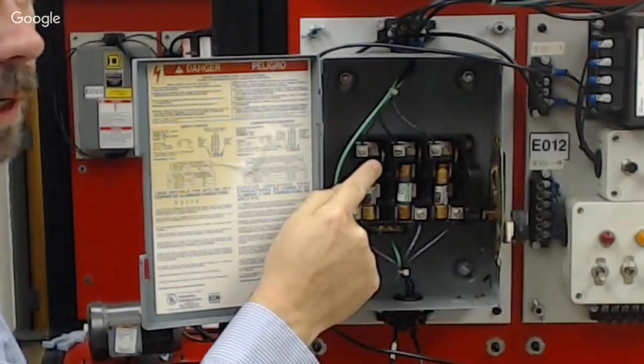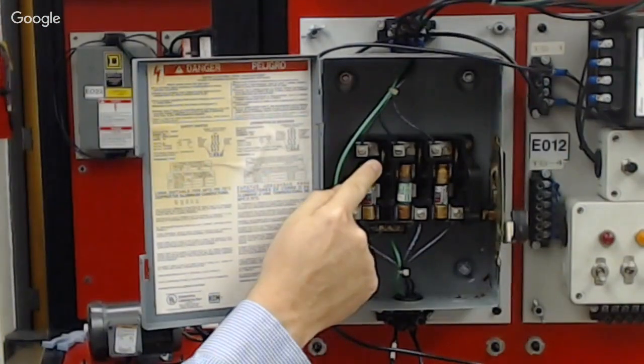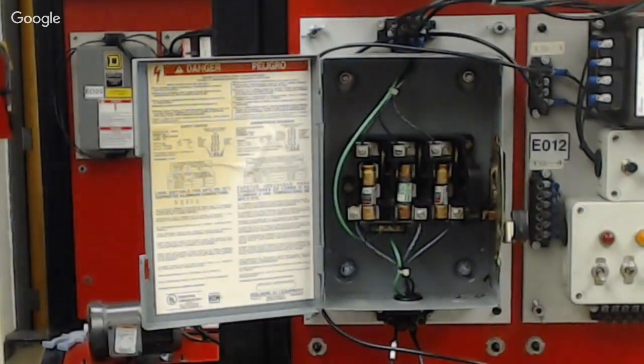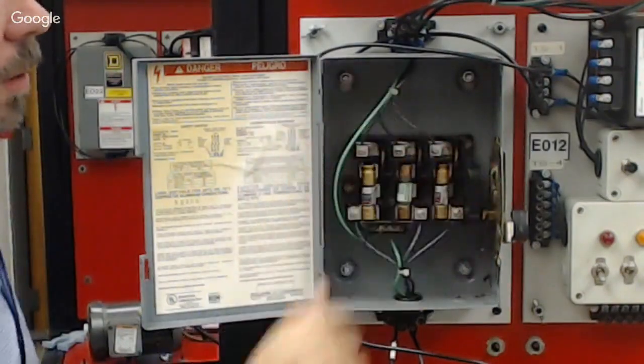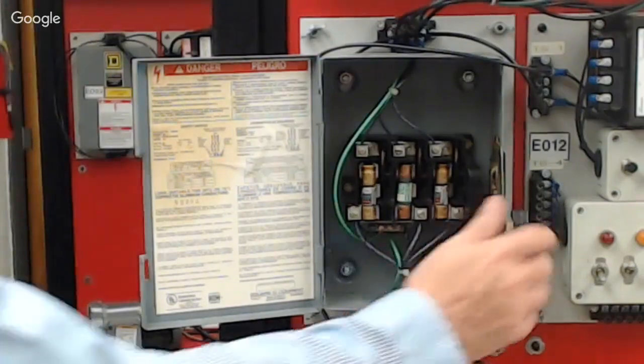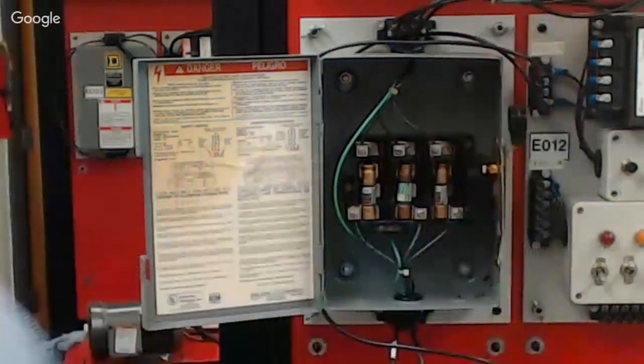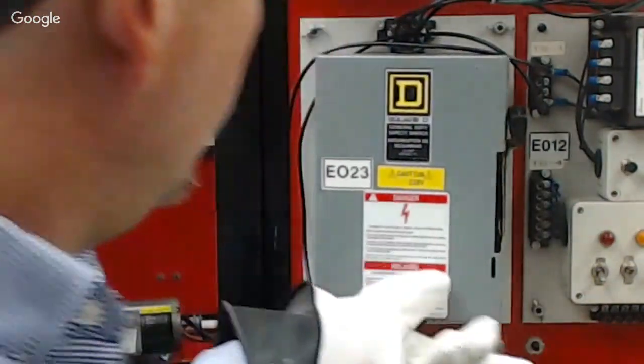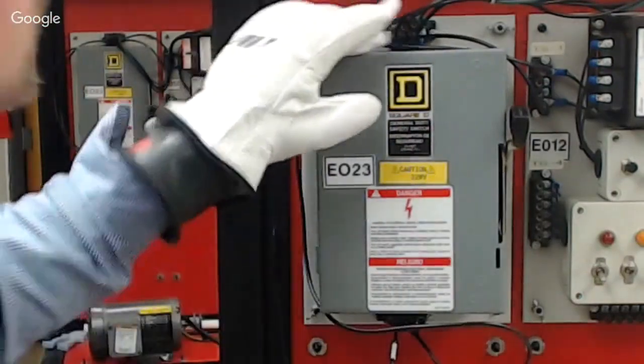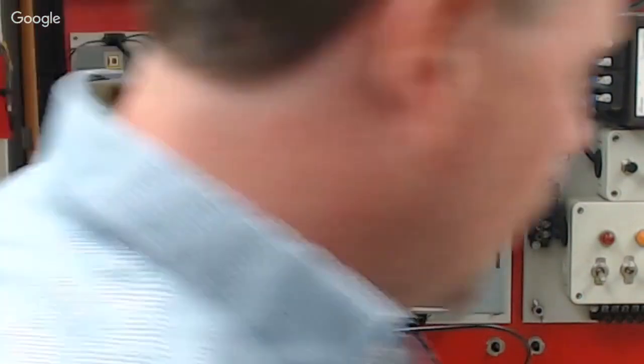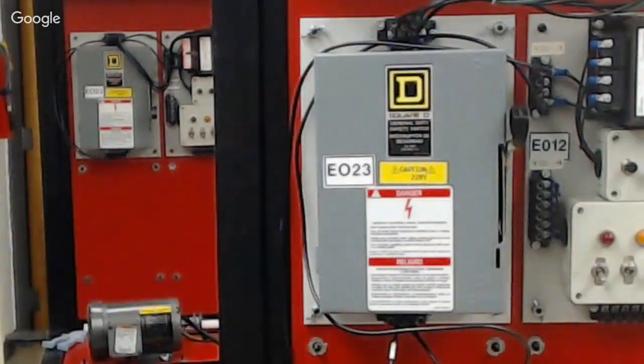If one of those sticks and you apply a load to this, this can actually overheat and melt and start an arc flash. So let's talk about the proper way to turn off a disconnect, and then we're going to use the cross-check method to check our fuses, and we're also going to ohm out a fuse. So with your arc flash stuff on, we're going to zoom back out.